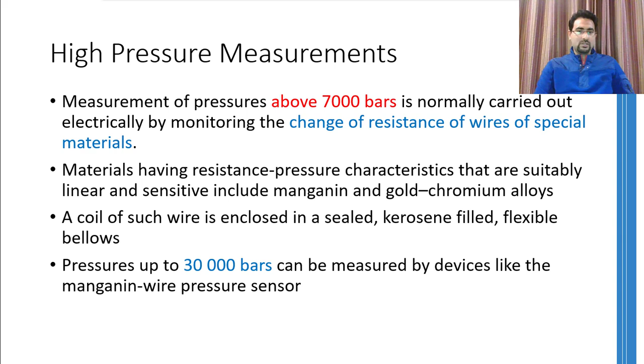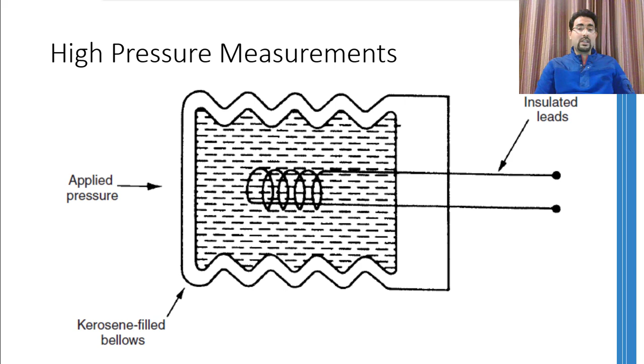Manganin and gold chromium alloys show considerably linear and sensitive pressure resistance characteristics. Therefore, wires made out of these materials are commonly employed for measuring high pressures. The construction of this kind of device is shown over here. A kerosene-filled bellow contains these special material wires, and if high pressure is applied on these bellows, then this pressure through the kerosene oil will be transferred to the wire and the resistance of the wires will change. Normally, these kinds of pressure measuring devices can measure pressures up to 30,000 bars.